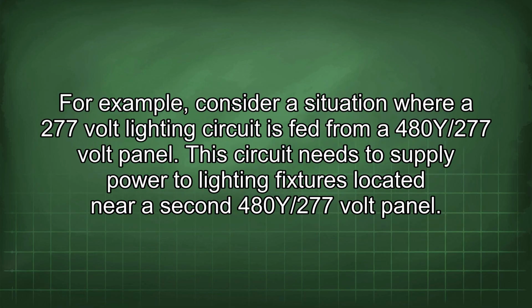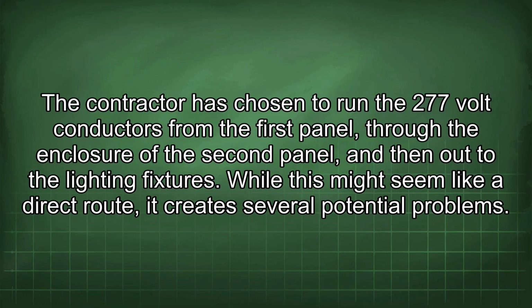For example, consider a situation where a 277-volt lighting circuit is fed from a 480Y/277-volt panel. This circuit needs to supply power to lighting fixtures located near a second 480Y/277-volt panel. The contractor has chosen to run the 277-volt conductors from the first panel through the enclosure of the second panel and then out to the lighting fixtures. While this might seem like a direct route, it creates several potential problems.